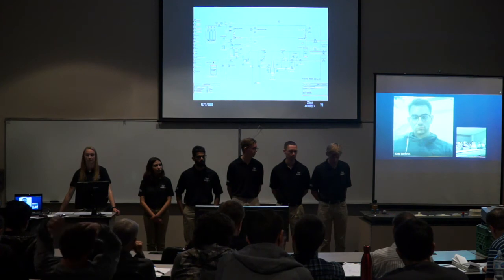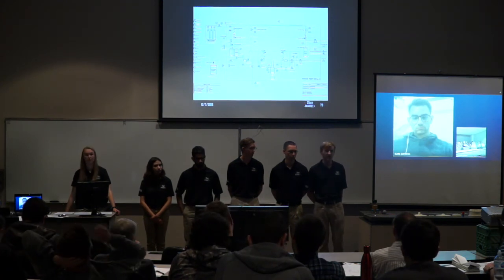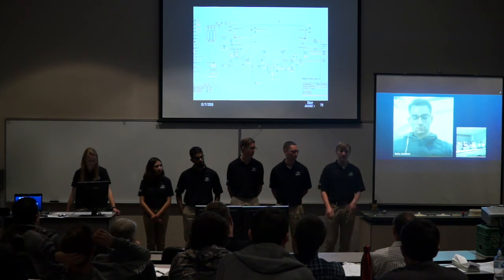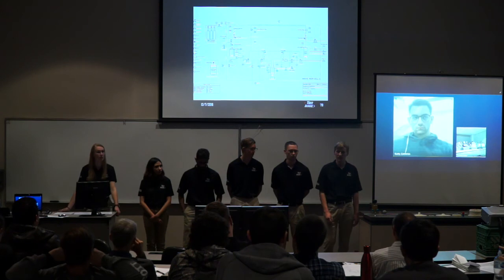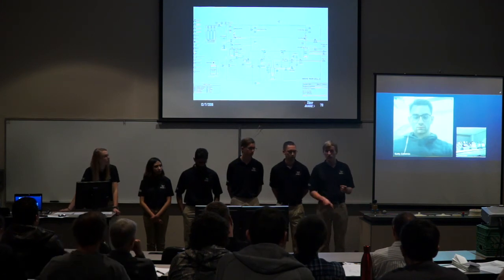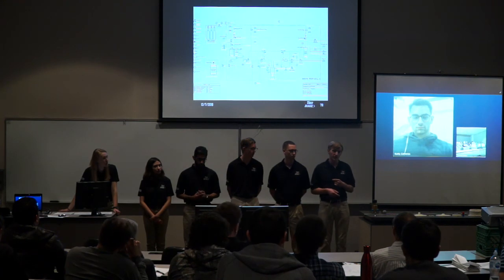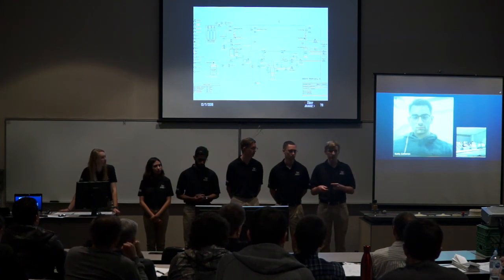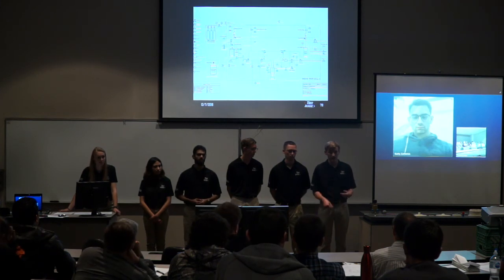Yeah. So I combine them together, so it's one source. I like having that rather than having to have the air compressor running that we had to do before. If we do end up seeing a very large drop during purge, where we can no longer actuate our pneumatic valves, I'll be throwing in accumulators near the purge valves, so hopefully that'll take the load off.